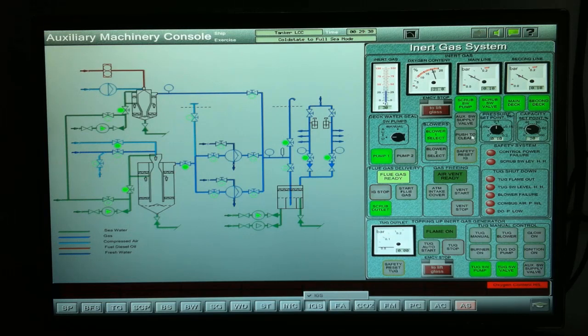Okay, I believe it's still not running. I need to rectify the... Oh, I forgot to open the flue gas valve. Okay, so we need to open this flue gas valve in order to rectify the alarm. So wait a little bit. Flue gas is ready. So once the pump is running, the blower is running. Okay, the oxygen content will be decreased below 8%. So everything is already normal.